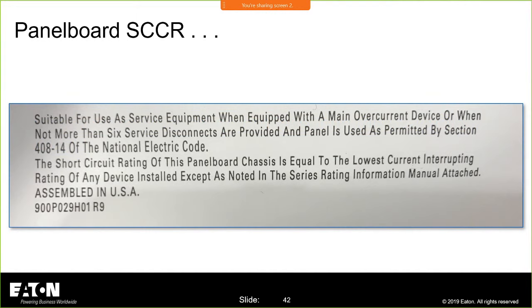This is the language from a panelboard label. What you'll notice is, it says right here, the short circuit current rating of this panelboard chassis is equal to the lowest current interrupting rating of any device installed, except as noted in the series rating information manual attached. If this is the case, if it's the lowest current interrupting rating of any device installed, that tells me that when you put this in the field and you buy the breakers that go in that panelboard and you put them in, you are determining the short circuit current rating of that assembly.